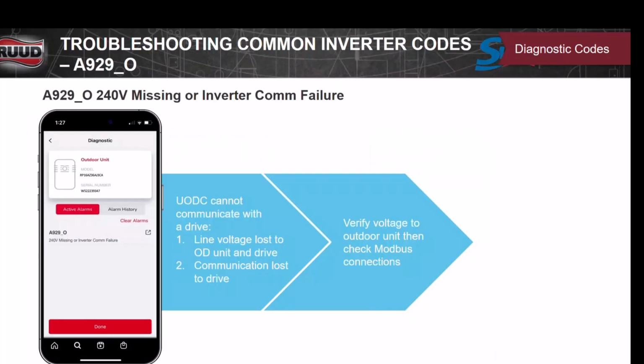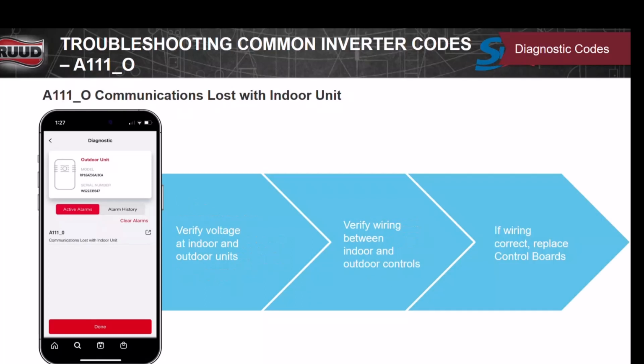So if we have an A929_O, that means 240 volts is missing at the inverter, and it cannot communicate with the drive. So we need to check line voltage to the outdoor unit. Verify that we have proper voltage from our Modbus over to the inverter so it can communicate. That's that first picture you guys took, right? Verify the voltage at the indoor unit and outdoor unit, verify the wiring between the 2 units, and then verify the correct wiring. If all that's good, you've checked it, and it's doing what it's supposed to, then at that point we'll change the board.